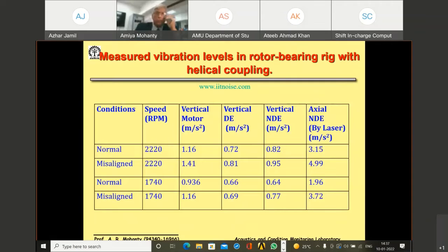So rate of temperature rise of coupling compared to bearing can be used as an indicator for incipient misalignment detection in shafts. The rise time should be measured within the time constant of the system so as not to capture the steady state temperature of the bearing housing. It has to be quick enough, because if it has reached steady state, there's no point - it has to be a faster response. This can be used in locations where it is cumbersome or difficult to instrument or access.